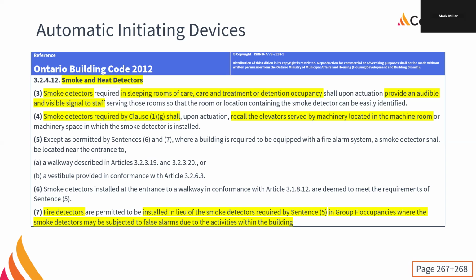Now, the modern elevators that I've been doing the last few years, yes, they call for it to recall the elevators. They recall it to the nearest floor. They don't bring it down to the ground floor if there's a fire in the elevator machine room. They just want it at the nearest floor with the doors locked open, because it's a lot safer not to be in the elevator if there's a fire in the elevator machine room. Yes, there are lots of redundancies and fail safes and all that, but we still go for it.